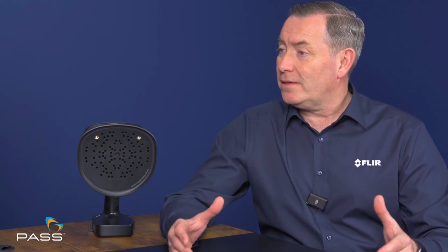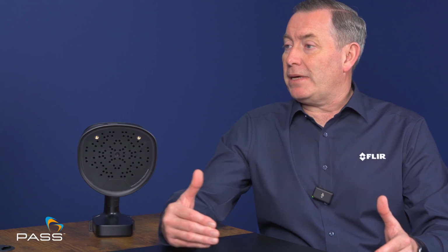Because ultimately, it's a question you might get asked as well. What happens when you fix all your leaks? Well, the simple fact is you never will. Because the nature of the beast is that when you have a bad leak, and it's the biggest contributor to your air loss, when you fix that leak, that then creates pressure in the system, which will make the smaller leaks a bit larger. So there's a continuous process of improvement with the leak location, identification and quantification.